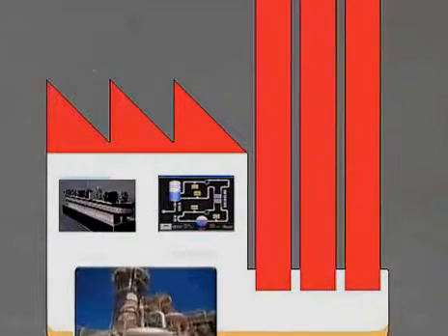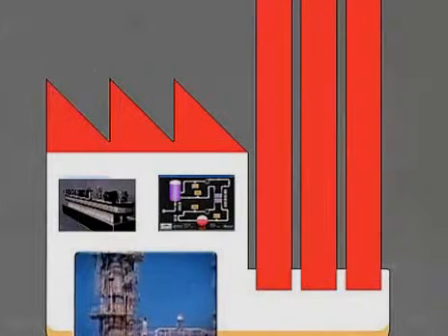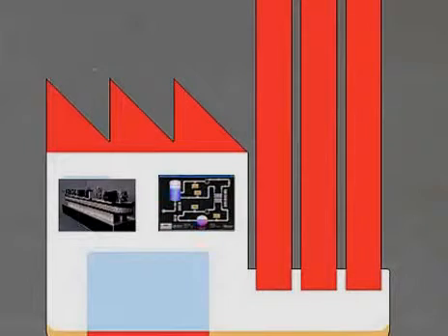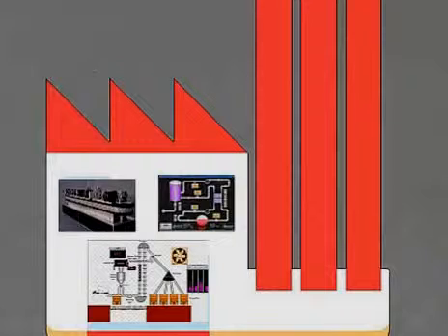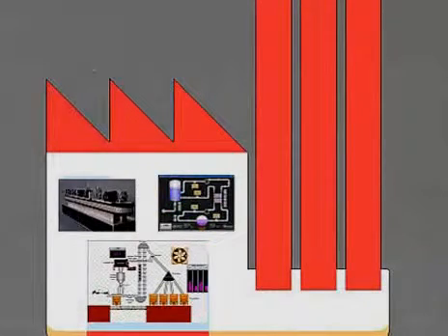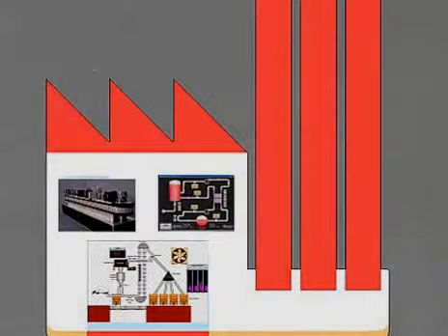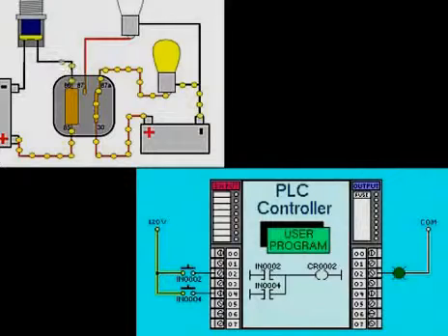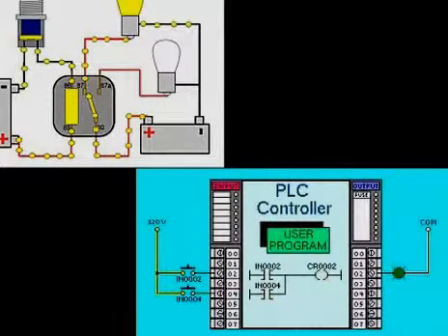The functionality of the PLC has evolved over the years to include sequential relay control, motion control, process control, distributed control systems, and networking. Older PLCs were capable of only handling discrete inputs and outputs, that is, on-off type signals, while today's systems can accept and generate analog voltages and currents, as well as a wide range of voltage levels and pulsed signals. PLCs are also designed to be rugged. Unlike their personal computer cousin, they can typically withstand vibration, shock, elevated temperatures, and electrical noise to which manufacturing equipment is exposed. Early PLCs were designed to replace relay logic systems. These PLCs were programmed in ladder logic, which strongly resembles a schematic diagram of relay logic. This program notation was chosen to reduce training demands for the existing technicians, since it was a familiar format used for electromechanical control panels.